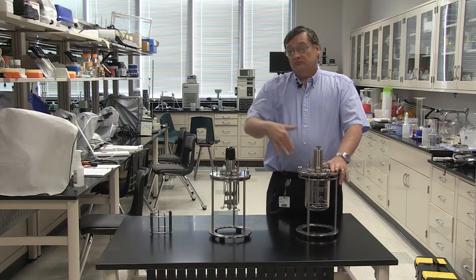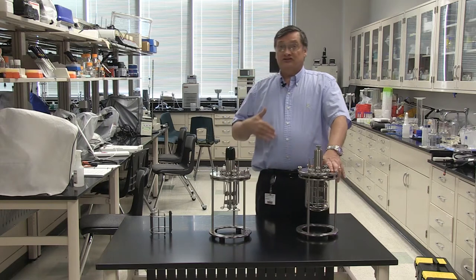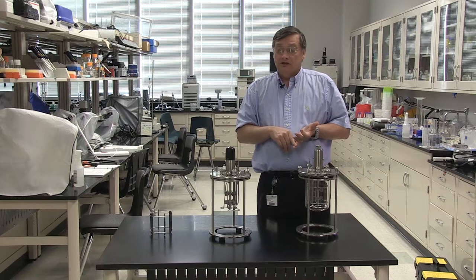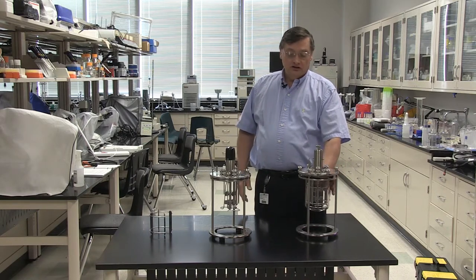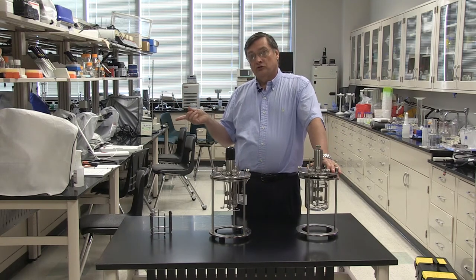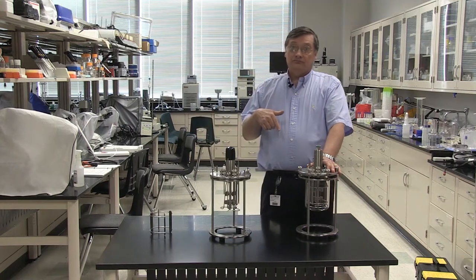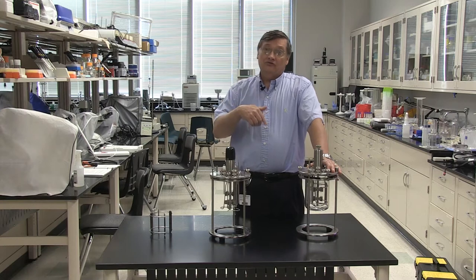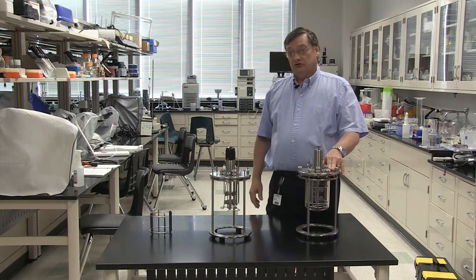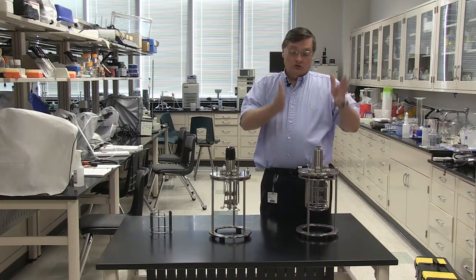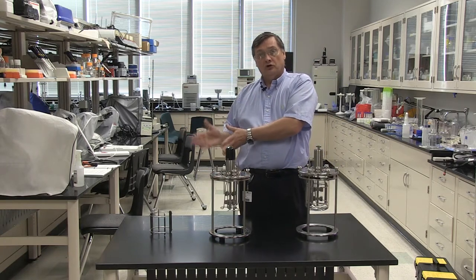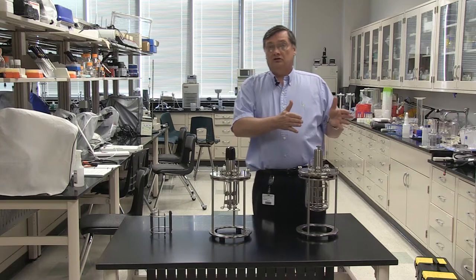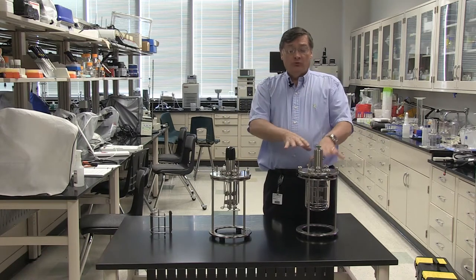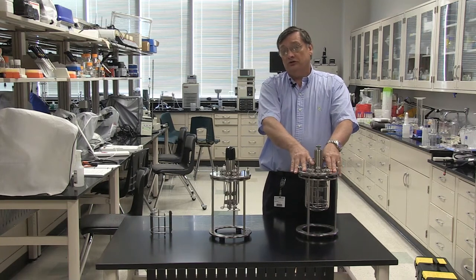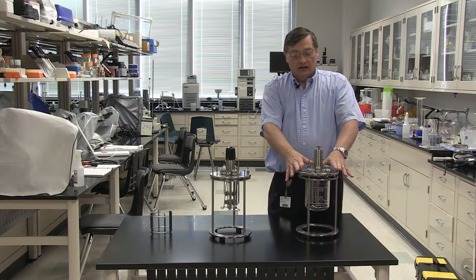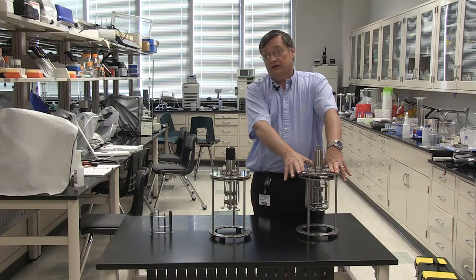Like I say, we call these methods of control, we call them control loops. So for instance, the temperature control loop requires a monitor, which would be a thermocouple that actually monitors the temperature in the vessel, sends that information to the control unit. The control unit then either warms the vessel if the temperature is too low, or can actually then cool the vessel if the temperature exceeds the desired temperature. So that would be the control loop: a monitor to send information to the control unit, and then some way for the control unit to control that. So when we actually assemble the vessel and hook it up to the control unit, we'll be looking at each one of those control loops.